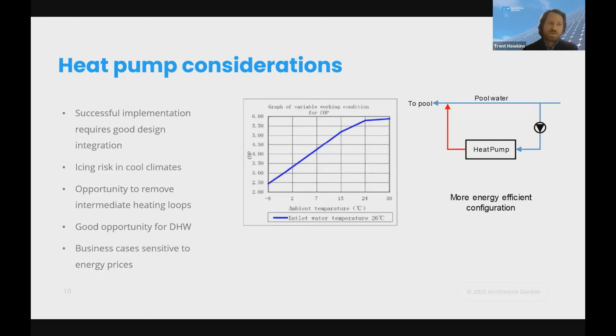There's also a good opportunity to consider removing intermediate heating loops. In the diagram, pool water comes in through a heat exchanger and is heated from a separate loop supplied by a heat pump. An alternative configuration, if your heat pump can accommodate it, is to directly heat the pool water from the heat pump itself.